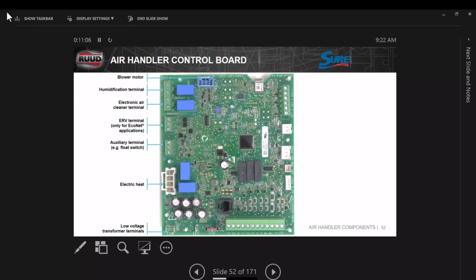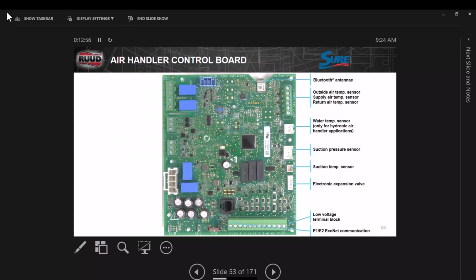Electric heat switches. Now, the electric heat, how many of you had a situation come up where the plug from the heat kit wouldn't plug into that board? We're dwindling through that right now, so we're probably not going to have to wait on it much longer. But the new heat kits, when you plug it into this board, it's going to automatically recognize what size heat kit. The heat kit has to end in a B, not a 1. So if you get a heat kit with a -1, it'll plug in, but it won't work because it's made for the non-Bluetooth units. The B means Bluetooth. So if you've got one of the mid-tier stuff with Bluetooth, make sure it has a -B on it. Again, Bluetooth antenna at the top there.